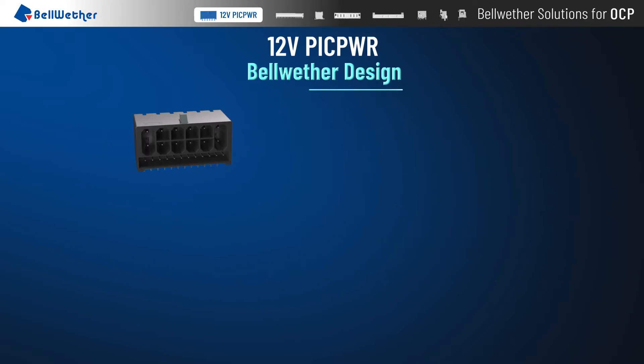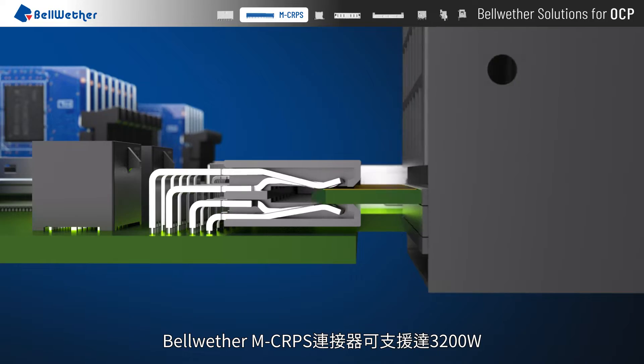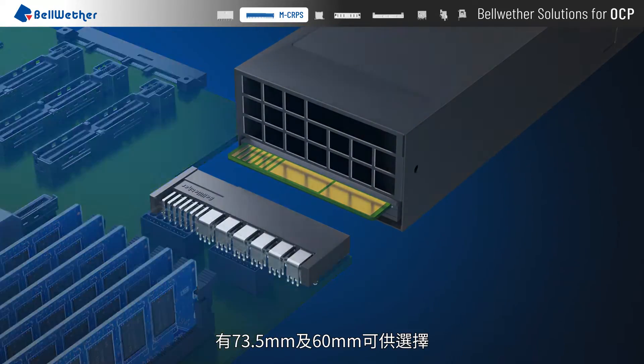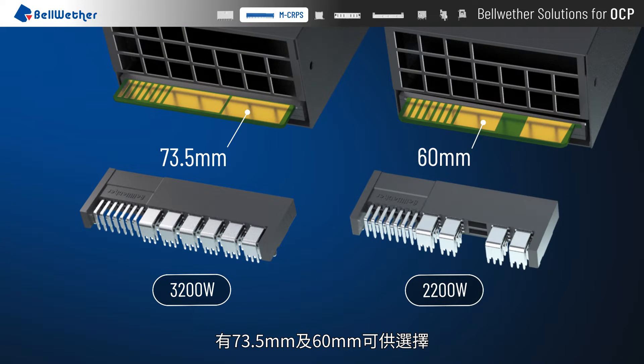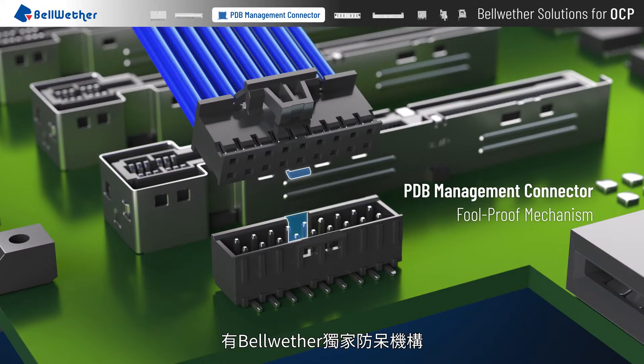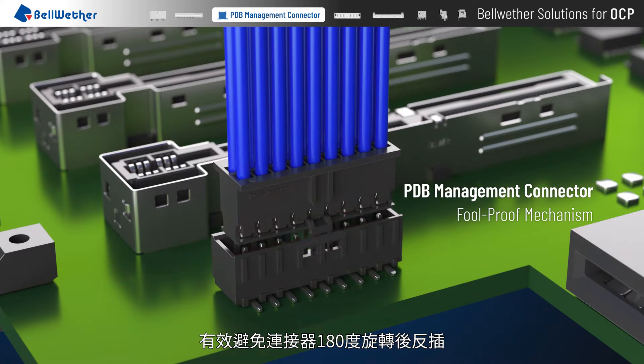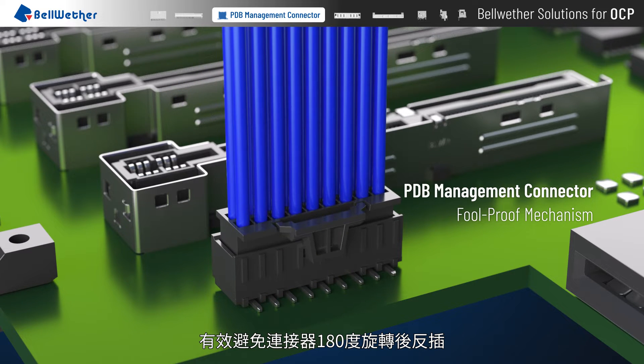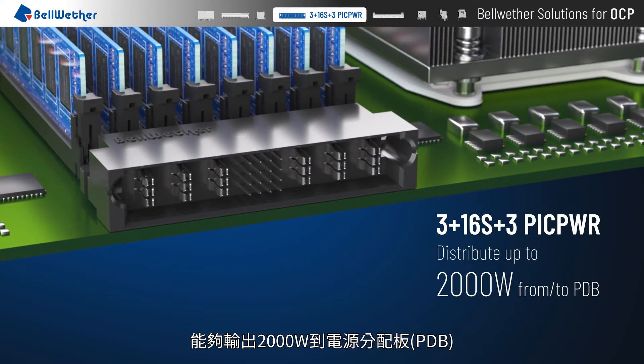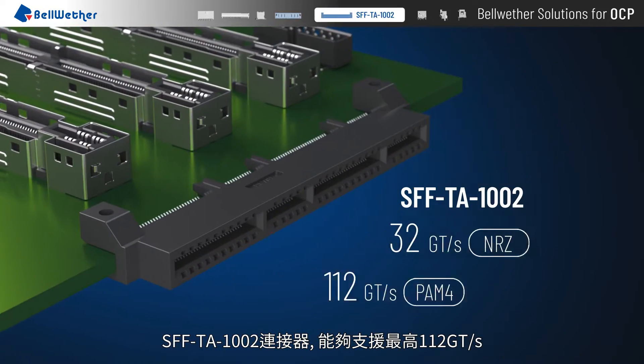Bellwether MCRPS supports up to 3200 watts. Both 73.5 millimeter and 60 millimeter connectors are available. PDB Management comes with an exclusive Bellwether foolproof mechanism to effectively prevent the connector from being inserted in reverse after rotating 180 degrees. The 3+16S+3 PICPWR distributes up to 2000 watts from the PDB.